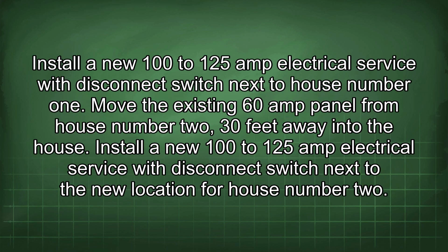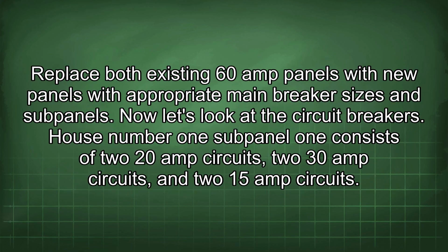Install a new 100 to 125 amp electrical service with disconnect switch next to house number 1. Move the existing 60 amp panel from house number 2, 30 feet away into the house. Install a new 100 to 125 amp electrical service with disconnect switch next to the new location for house number 2. Replace both existing 60 amp panels with new panels with appropriate main breaker sizes and subpanels.